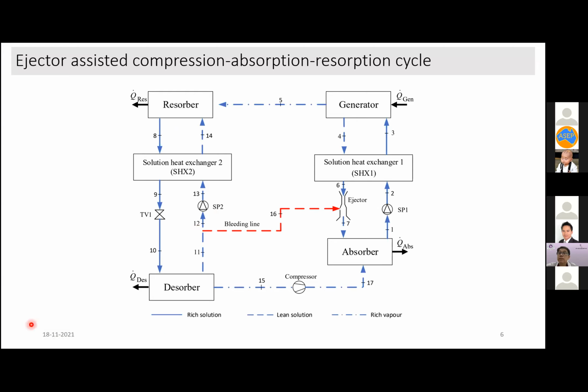In this configuration there is no rectifier, so the mass fraction of the vapor leaving the generator at state 5 differs from the mass fraction of the vapor leaving the desorber at state 15. This results in an unbalancing of the mass in the cycle. To balance the overall mass, a bleeding line is used, operating at desorber pressure. In order to boost the pressure of this bleeding line, the ejector is integrated.